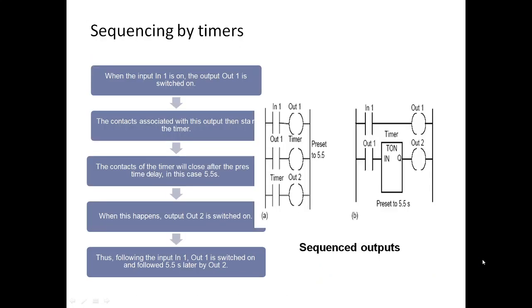Sequencing by timers. When input 1 is on, output 1 is switched on. The contacts associated with the output start the timer. The contacts of timer will close after preset time delay of 5.5 seconds. When this happens, output 2 is switched on. Thus following input 1, output 1 is switched on and followed 5.5 seconds later by output 2. This is called a sequence of outputs.